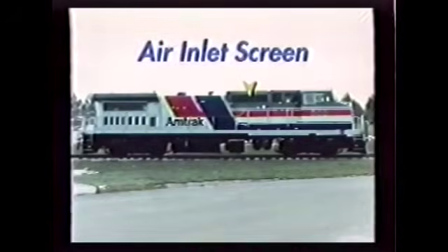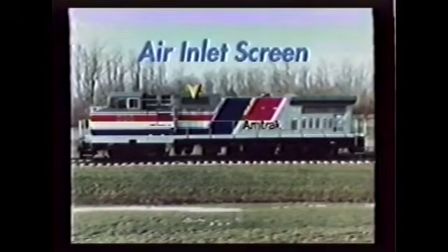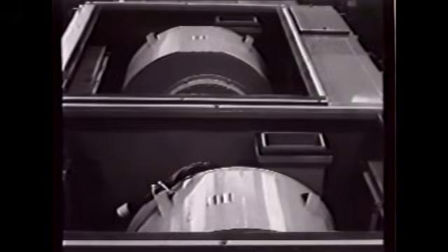Next, we have the auxiliary air filters. These filters provide clean air for the electronic equipment and should be changed during the 180-day inspection. The V-screen at the top of the locomotive contains plastic spin filters for the front equipment blowers. An identical inlet screen is on the opposite side of the locomotive. A three-phase AC motor drives the equipment blowers. The computers calculate required cooling air and run the blowers at 1/4, 1/2, or full speed. Blower usage is kept to a minimum, further increasing the fuel efficiency of the Dash 8.